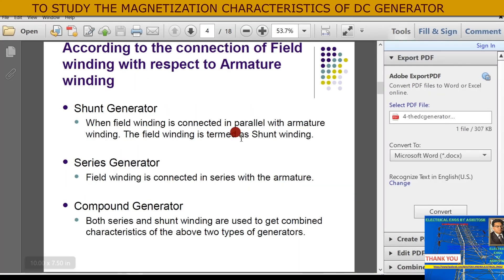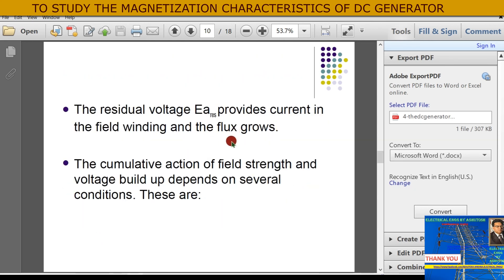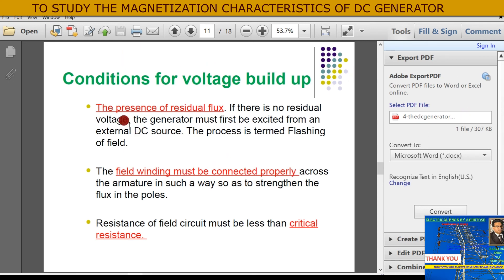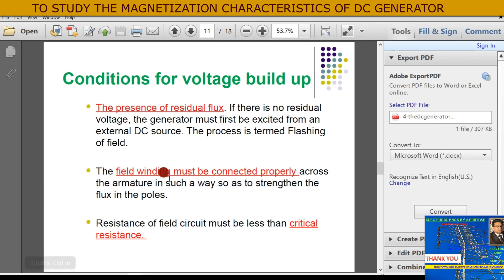Here are the conditions for voltage buildup. First: there must be residual flux in the field winding. If there is no residual voltage, the generator must first be excited from an external DC source — this process is called flashing of the field. Second: the field winding must be connected properly across the armature to strengthen the flux in the poles. Third: the resistance of the field circuit must be less than the critical resistance.